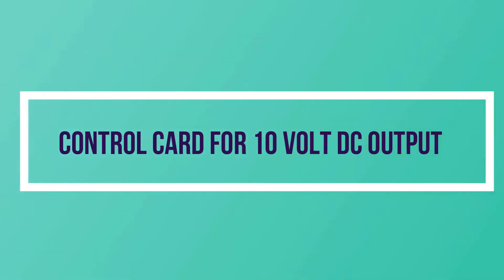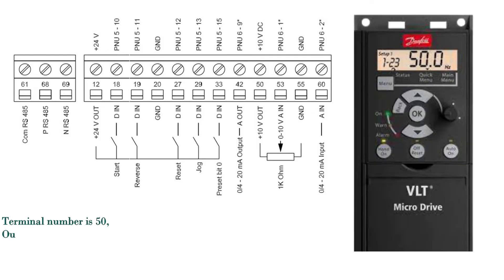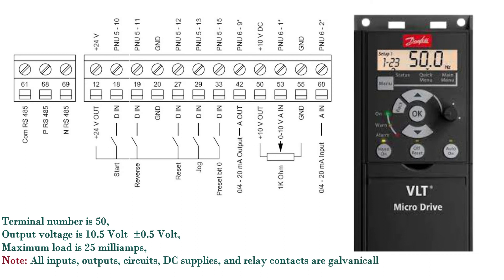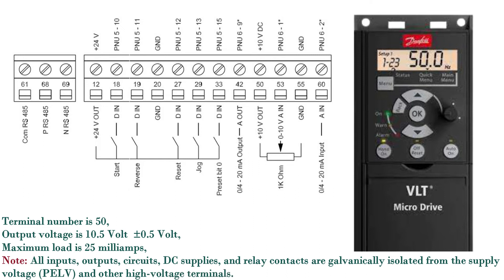Control card for 10 volt DC output: terminal number is 50; output voltage is 10.5 volt ±0.5 volt; maximum load is 25 milliamps. Note: all inputs, outputs, circuits, DC supplies and relay contacts are galvanically isolated from the supply voltage (PELV) and other high voltage terminals.